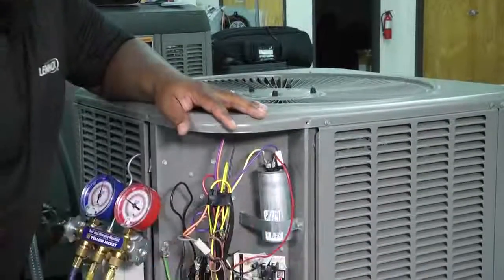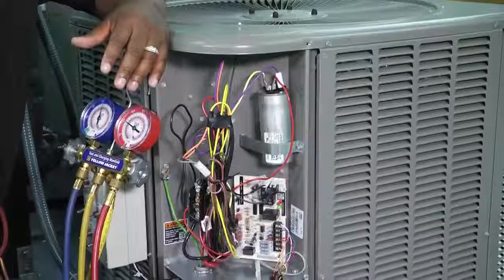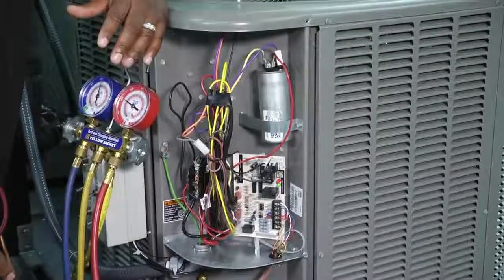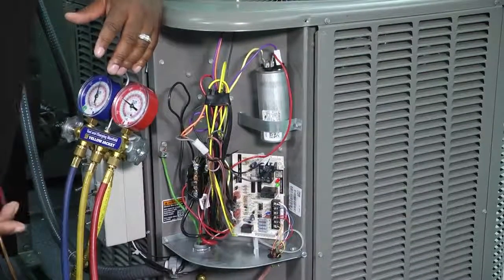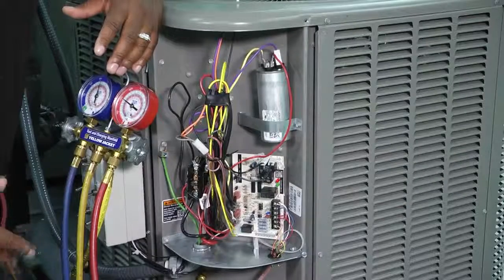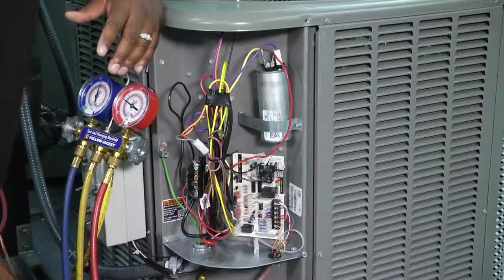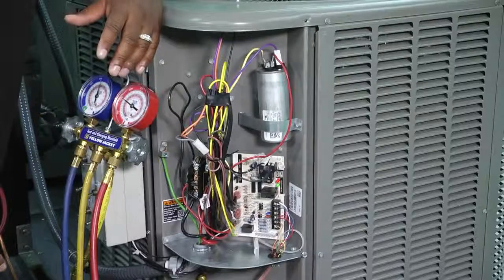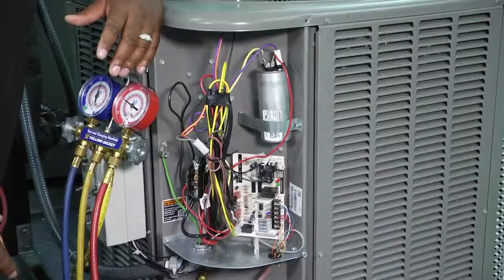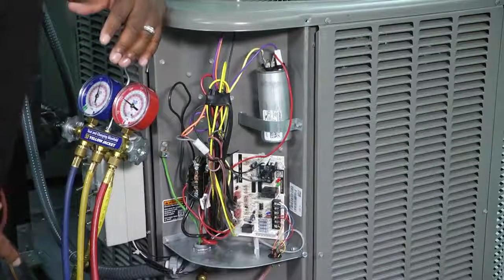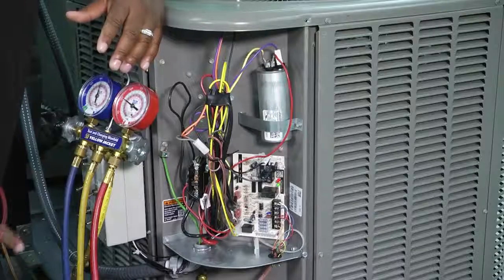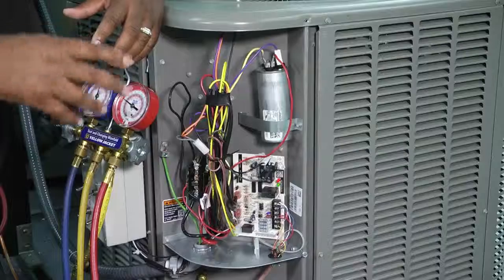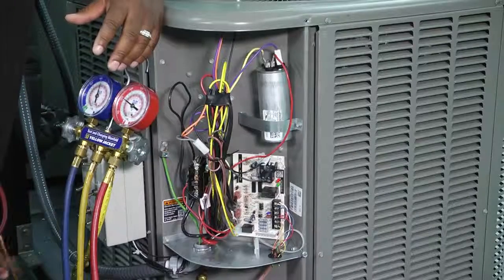Now, when it comes to cleaning the coils, there's a lot of products out on the market that your local supply houses may have. Your company may stock your truck with one that they recommend and they use. But one of the things that's important is we definitely need to have a conversation with our homeowners about how often they should clean their coils. Now, a lot of people may not want to do that themselves, and here's a great opportunity for the technician to say, hey, this is a good reason for you to be a part of our preventative maintenance program, where we can come out a couple times a year and actually check that for you.